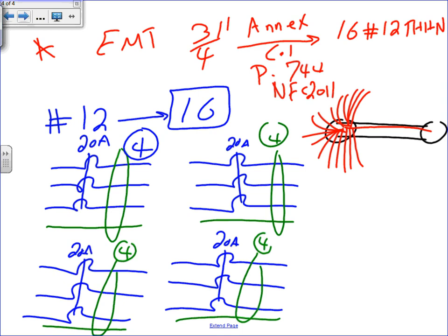What's the value of doing it? Yeah, because we lost reliability now, right? One of them tripped, the rest went down. Well, because people got burned, and burned equipment, in multi-wire branch circuits. If they were not tied together and I'm working on this circuit, I disconnect it, working on this equipment, guess what? The neutral is still hot from the other two circuits. So people were zapped by current in the neutral, because that neutral is operated by the three circuit breakers. If you turn one of them off, there will still be current in that neutral coming from the other two.